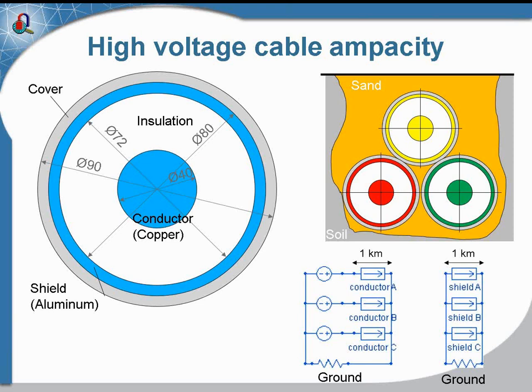Today we will review the case of a three-phase underground cable, and the task will be to calculate the ampacity. The cable is buried underground in a trench filled with sand. When you apply voltage, current flows in the cable, the cable heats up, and the ampacity is limited by the cable temperature. The high-voltage cable consists of the central conductor, the insulation layer, the conducting shield, and the insulation cover.